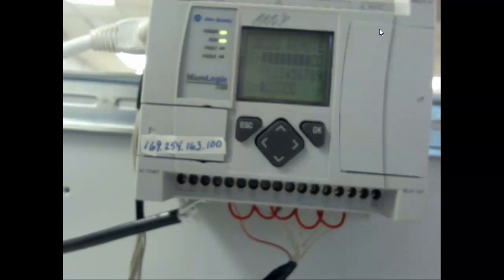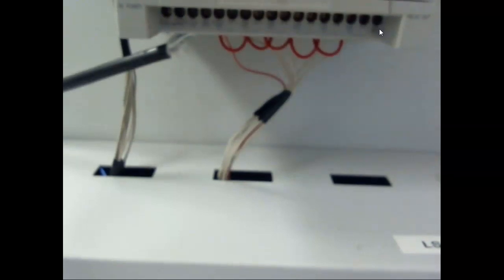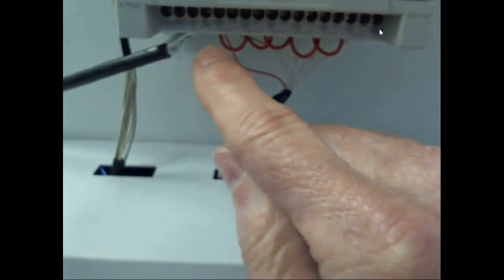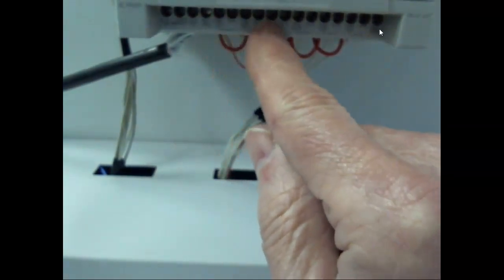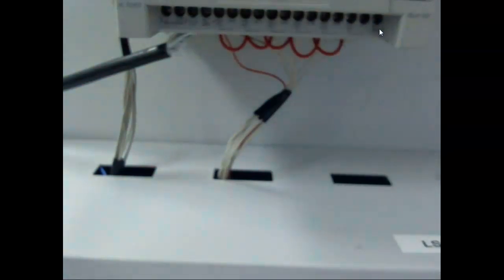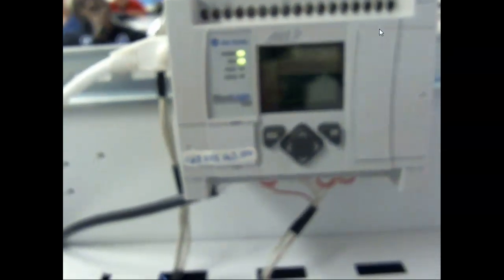Can y'all see that? This guy here, if I can zoom in on the outputs. Every loop is an output. So it's got 1, 2, 3, 4, 5, 6 outputs. My inputs, I don't know if I can show y'all that or not. They're up across the top. Just focus in. It's got 2 commons, and that's what happened. One of my commons came loose, which we're going to talk about in a second.